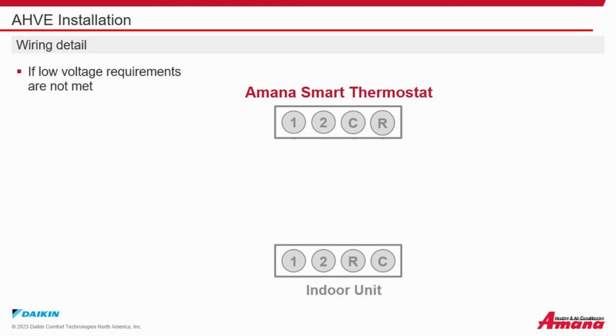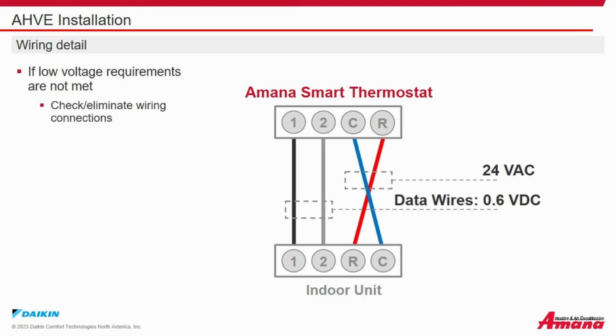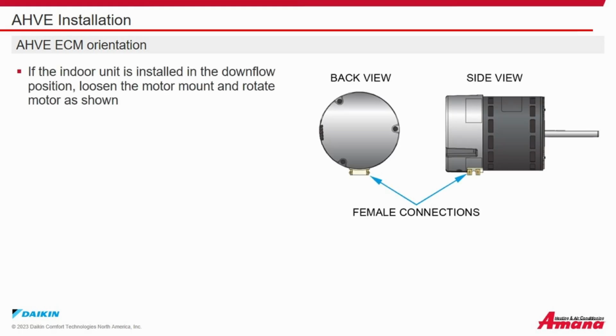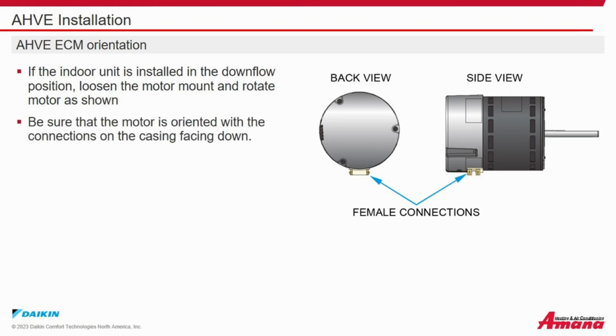Wiring detail. If low voltage requirements are not met, check or eliminate the wiring connections, or if necessary, replace the wiring. 18 gauge stranded is recommended. AHVE ECM motor orientation. If the indoor unit is installed in the downflow position, loosen the motor mount and rotate the motor as shown. Be sure that the motor is oriented with the connections on the motor casing facing down.